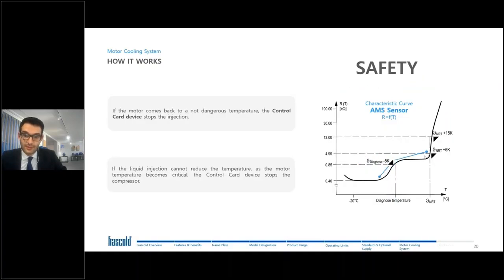Here is what I said before, the area, the zone, where we can act to prevent motor overheating. It's all this part, and I repeat, it's from 70 to 100 degrees. As I said before, even if the injection is on, but the temperature continues to increase, clearly at that point we have to stop the compressor.